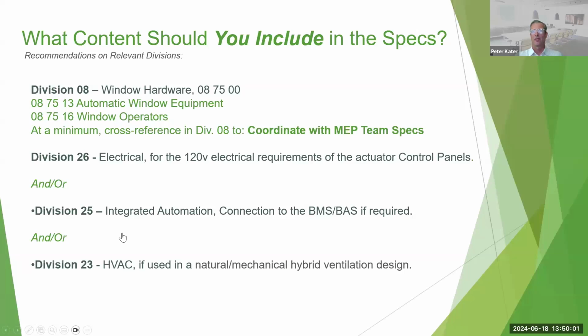Division 25 addresses system integration, where you would connect a building management system, building automation system, to the natural ventilation controller. Division 23, which covers mechanical ventilation, or ventilation generally, is where you would typically put the content for the natural ventilation control system. Often Division 25 content's not needed, because you can put all of that integration spec content into Division 23 as well. So typically we'll see Division 8 for the hardware, and then Division 23 if you have the intelligent control aspect of the system.